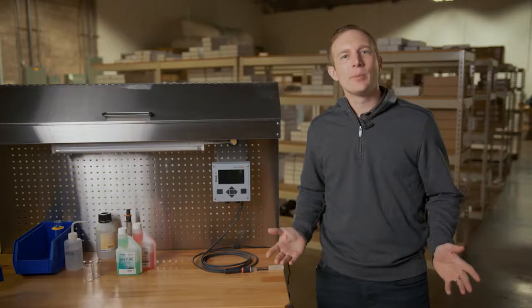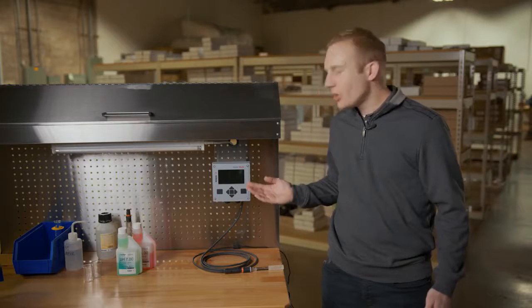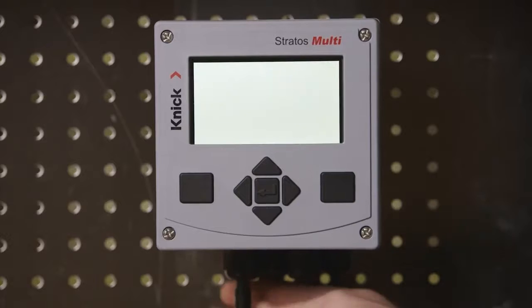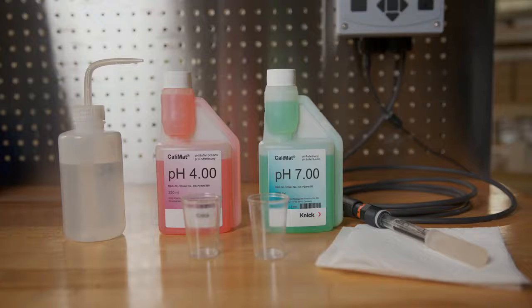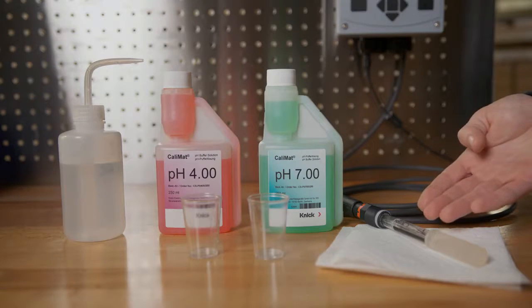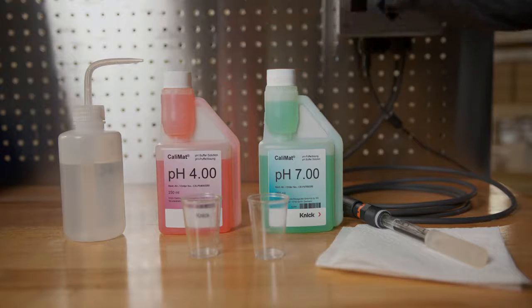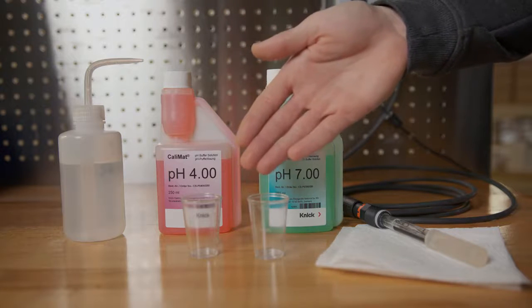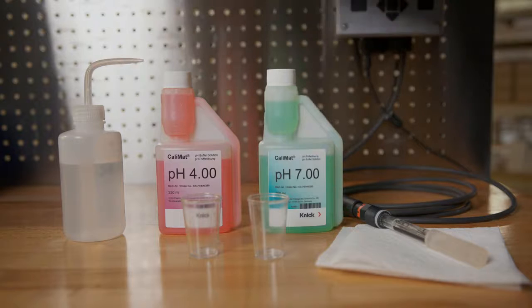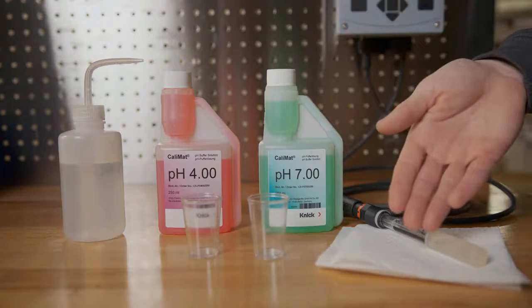To perform a calibration, you will need a Stratos multi-transmitter that has been powered up with a MemoSense cable connected, a MemoSense pH sensor, at least 2 buffers with clean containers to pour them in, rinsing water, and a clean cloth to dab the sensor dry.